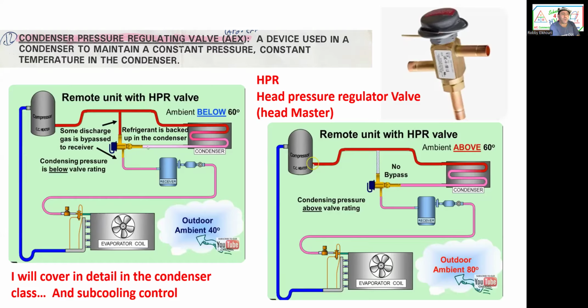So if outside temperature is 40 degrees, what's going to happen? Now look at the small box. Look at my hand. We have high pressure here, low pressure here. On a very cold day, what's going to happen to the high pressure here? It's going to drop, causing the low pressure to drop. Because high pressure drops, low pressure drops, nothing will work. We cannot remove heat anymore if the low pressure is so low. Compressor is going to cycle on, off, on low pressure. So we have to maintain the high pressure properly. And there are many ways to maintain subcooling or maintain the head pressure. One of the ways is the HPR valve. It will bypass some of the freon, some of the hot gas vapor, to the receiver to keep pressure high.